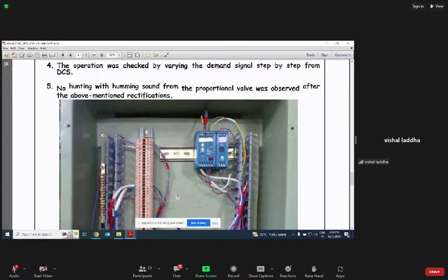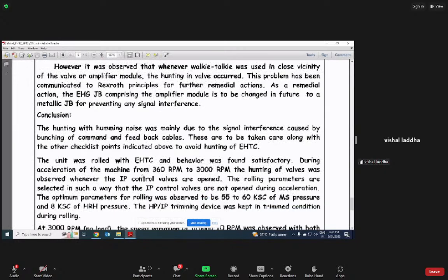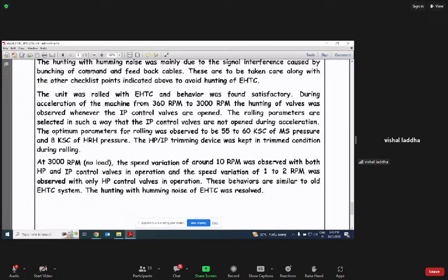So these steps need to be taken care of at any station, because nowadays hunting may be due to oil quality also, because our proportional valve is very delicate due to moisture and oil quality. So if hunting is observed, first we need to check oil quality. If oil quality is okay, moisture is okay, then we need to consider the shielding of the proportional valve, the shielding of the amplifier module, and then check cable noise also. So all the things need to be taken care of, then definitely the hunting problem will be resolved. And after that modification, the rpm and all are smooth. So this is all about the EHTC case study.